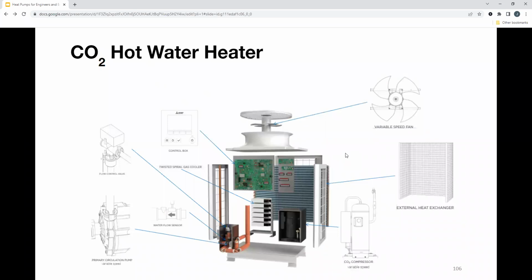This is just an exploded view of this domestic hot water heat pump, right? You have your CO2 compressor right here. You have your external heat exchangers, variable speed fan, control box, control panels here, right? And inside you have your primary circulation pump, you have your flow control valve, water sensor, and then lastly, you have your twisted spiral gas cooler, right? So it's basically absorbing heat out of the air, absorbing coldness out of the refrigerant and heating up the water that way.